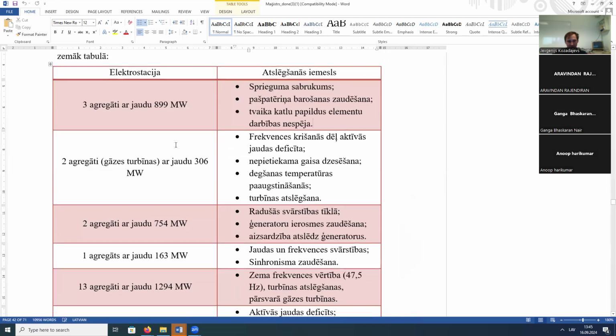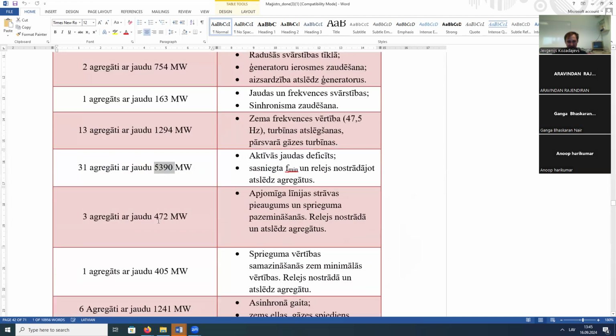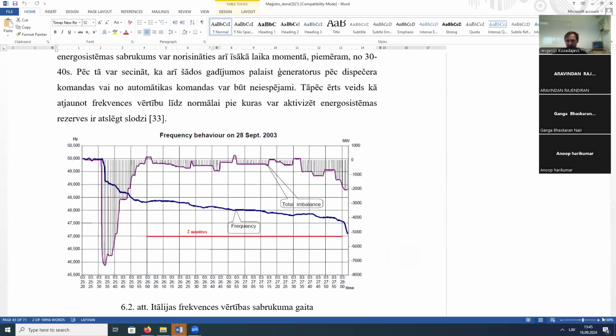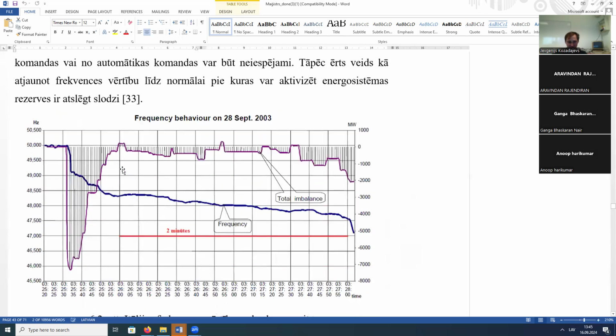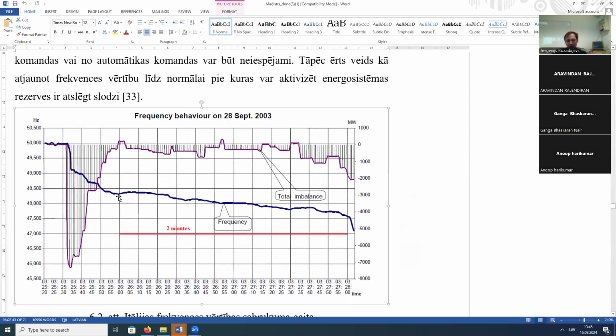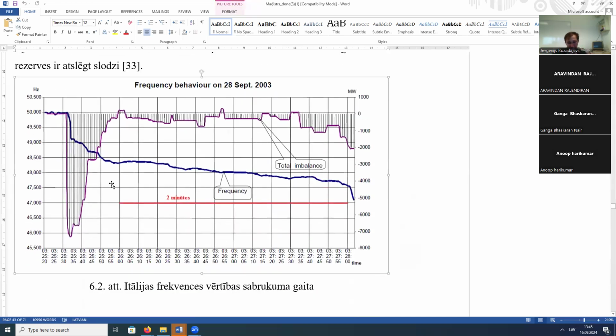Here is a list of number and total power. Disconnect, disconnect, disconnect. So the problem: we have a system in balance, very good at this time moment, but frequency is low, and it is low for 30 seconds, from this time period to this time period. Yes, 40 seconds, it is low for 40 seconds. And generators started to disconnect due to the low frequency.